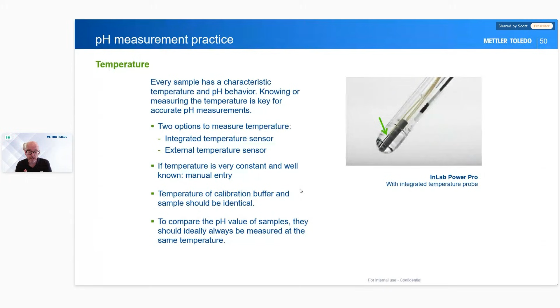Next one is making sure we've got the right temperature. So every sample has a characteristic temperature. Knowing and measuring the temperature is key for pH measurements. Lots of our electrodes have temperature sensors built in, like this one, the Power Pro, which has an integrated temperature sensor. And it's really good to make sure that the temperature is known and well constant. And if you can't do that with an integrated temperature sensor, then you should measure the temperature and type it into your pH meter as you're taking those pH measurements.